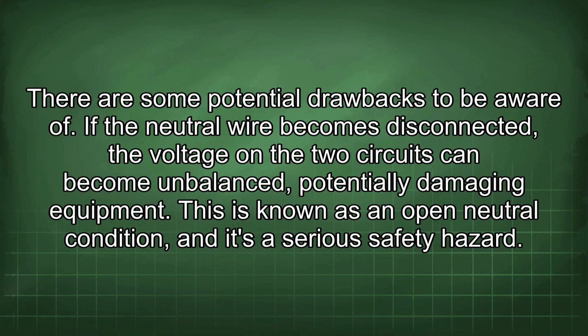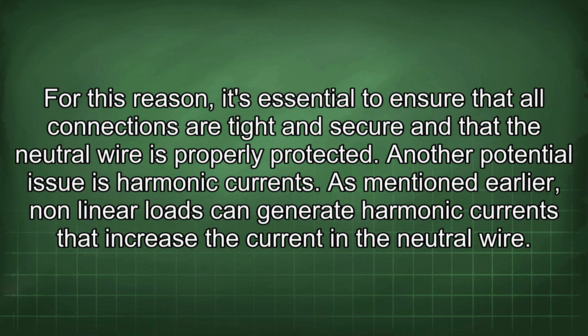If the neutral wire becomes disconnected, the voltage on the two circuits can become unbalanced, potentially damaging equipment. This is known as an open neutral condition, and it's a serious safety hazard. For this reason, it's essential to ensure that all connections are tight and secure and that the neutral wire is properly protected.